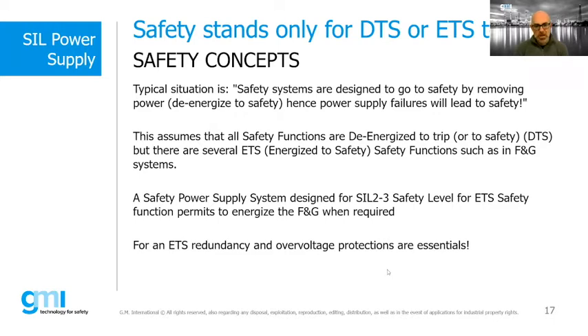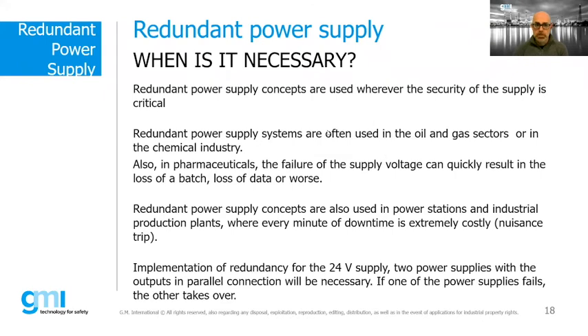A safety power supply is designed to guarantee a SIL2 or SIL3 safety level also for energized to safety applications, which need to energize the load on request. Well, for this type of application, redundancy and overvoltage protection are essential. A power supply redundancy system must be used when the safety of the power supply is essential. For this reason, the redundant power supply systems are used in critical sectors such as oil and gas or pharmaceuticals, and in all those applications where the loss of power supply translates into the loss of sensitive information, or in all those applications where the certainty of having a correct power supply on request is fundamental. It must also be used in all systems where every minute of production downtime is extremely costly.